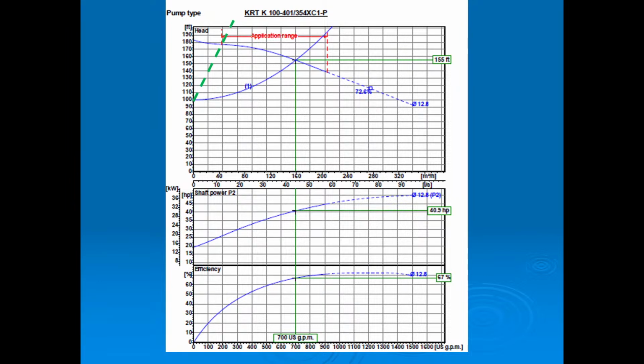That impeller's spinning. If we don't have quite as much head on it, what's going to happen? That pump's going to slide out to the right on that curve. When it slides out to the right, it's going to require more horsepower. When it goes to more horsepower, the line goes dashed. Therefore, whatever motor we selected on that impeller curve can't handle that duty condition. That's why it's dashed.